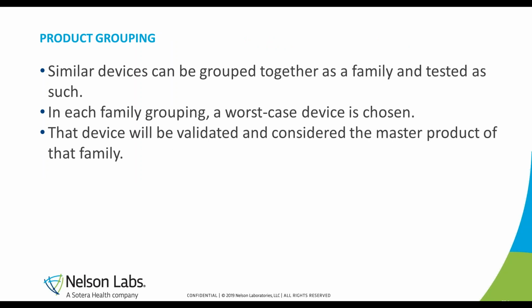As with any manufacturing process, product grouping and determination of a master product or worst-case representative device from each group is recommended. This is recommended to reduce the amount of validation required. Similar devices can be grouped together as a family and tested as such. From each family, a worst-case device or master product is commonly selected and documented with justification or rationale as to the worst-case conditions. The master device is then validated and represents the family in total.